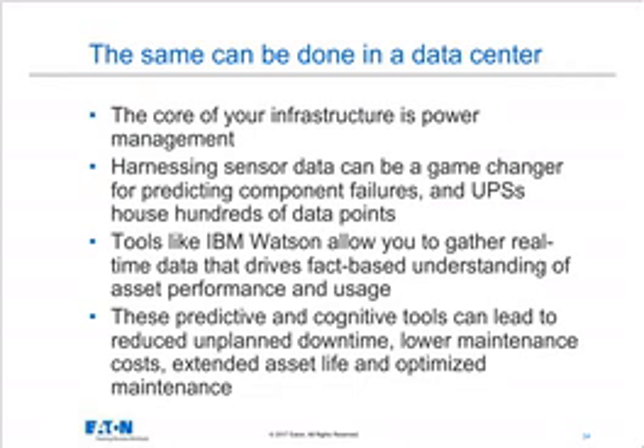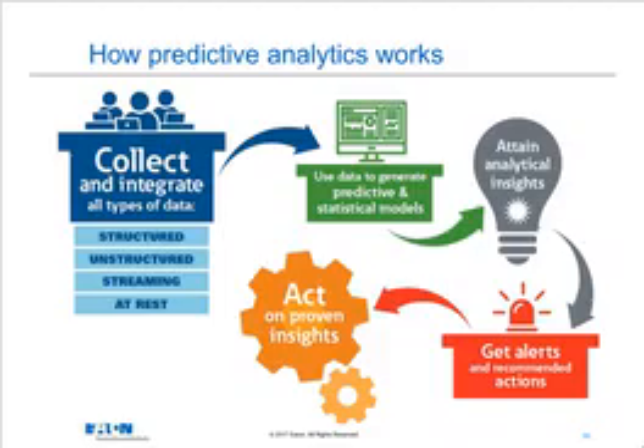In order to do what we want to do here, we find it's going to be necessary to monitor some 300 different data points or data streams so that we can gather a great deal of information from a lot of UPSs that are actually operating in the field and start to put together a data analysis package that will help to predict what's going to happen. So here you even see tools like IBM Watson, which are ideal for and designed for the artificial intelligence necessary to start down this path. So these predictive and cognitive tools can lead to reduction in unplanned downtime, which is extremely important. Also, lower maintenance costs. If I can do maintenance during a predefined window rather than as an emergency after a failure, it's going to cost a lot less for the end user and for their enterprise.